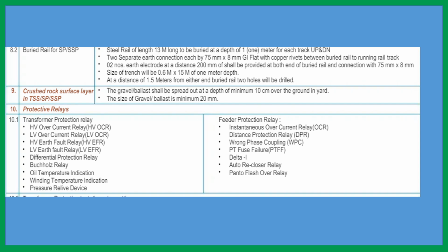PT fuse failure. If the PT fuse fails, then one relay is the delta I relay. For high resistive fault, delta I relay will act. I have told what delta I is already. Auto reclosure relay. Our system is, if the feeder circuit trips, then it will close, somewhere once, somewhere twice. But with auto reclose, it will close automatically after tripping once. Then it will lock and open. Lock and open means there is some fault. If it trips twice, it has tripped, automatically closed, and tripped again, that means there may be a fault. So there is a need of fault isolation.